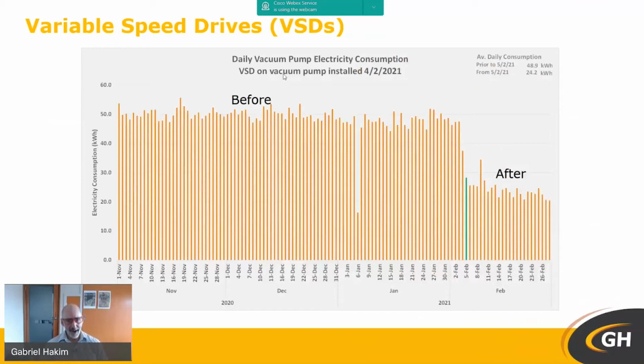This is a farm in Western Victoria, which has just installed a VSD on a vacuum pump. The vacuum pump was a blower type of vacuum pump. The dairy is a 50-unit rotary with cup removers, milking nearly 600 cows. The average daily consumption of the vacuum pump was around 49 kilowatt hours a day. The VSD was installed on the 4th of February, and after that, the daily consumption almost halved.